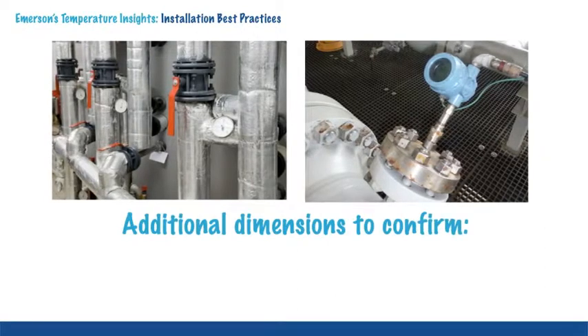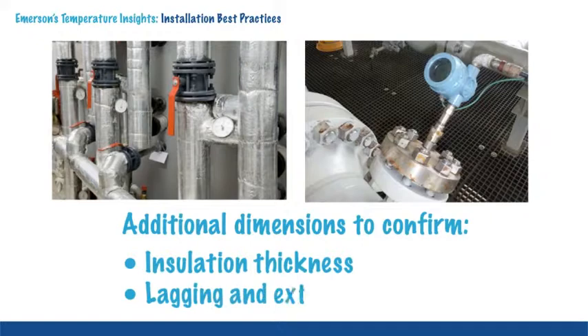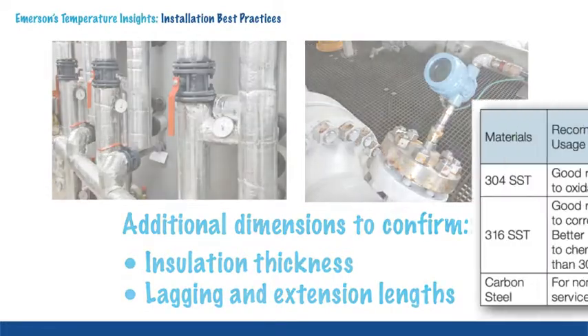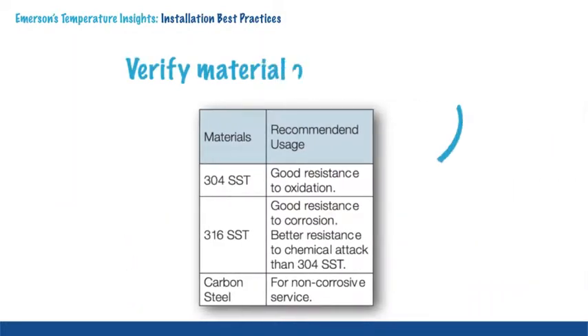The installation technician should now verify the Thermowell provided has the correct insertion length for the pipe or vessel. Other Thermowell dimensions may be verified by considering insulation thickness, lagging length, and length of any required extensions to protrude through the insulation layer. It is important to verify the material of construction of the Thermowell is compatible with the pipe or vessel and the process.